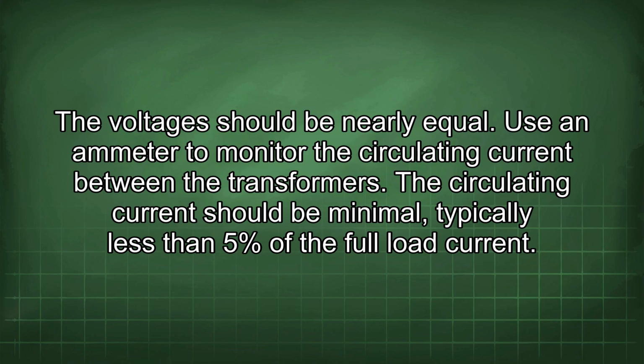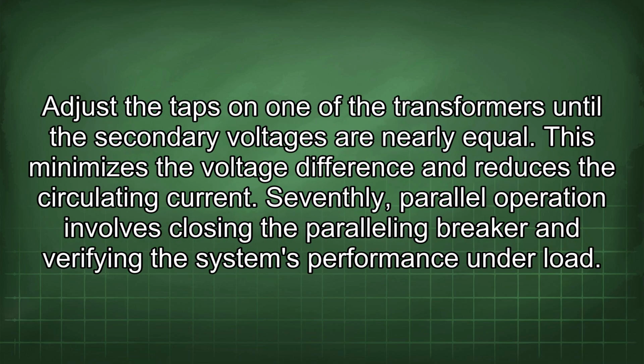Use an ammeter to monitor the circulating current between the transformers. The circulating current should be minimal, typically less than 5% of the full load current. Adjust the tap on one of the transformers until the secondary voltages are nearly equal. This minimizes the voltage difference and reduces the circulating current.